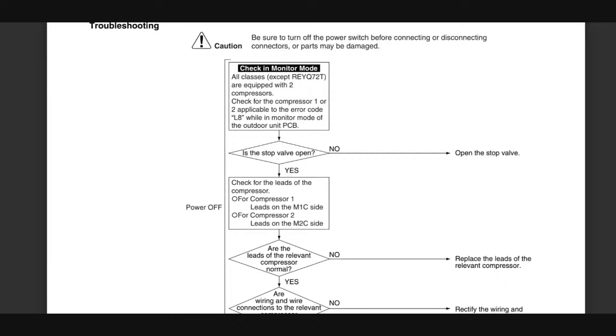In my opinion, I would recommend your outdoor unit code overrides any other codes. So if you've got something at the indoor giving a code and maybe that leads you to checking the outdoor unit and it has a separate code, prioritize that outdoor unit's code first. Deal with that indoor unit code later, because a lot of the time it is the outdoor unit's problem that is generating whatever you're seeing at the indoor, even if several indoors are doing it, or say you've got 8 indoors and only 1 is giving you this code. That's fine. The code on the outdoor, fix it first. Sometimes that outdoor code will redirect you back to the indoor too.